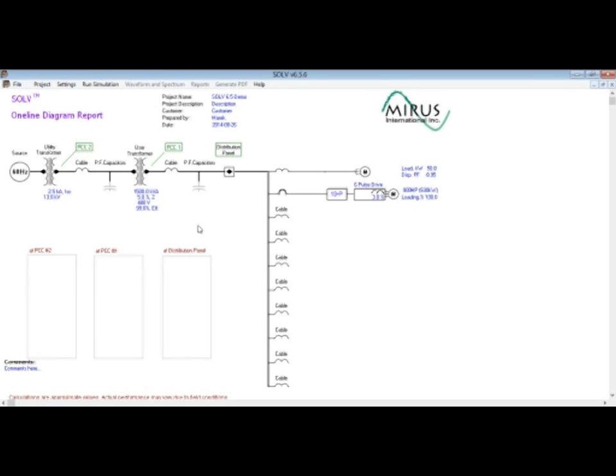A few more questions. Do system power factor correction capacitors on the main bus have an effect on your filters? Not too much. Our filter is designed with high impedance of the blocking reactor, so technically there is no interaction with anything that is upstream. There is some effect of harmonics coming to the filter when the voltage distortion upstream is very high, like 18% voltage distortion, then we have some more current going inside the filter. But we have no records of any instabilities in the system or interaction with power factor correction capacitors.